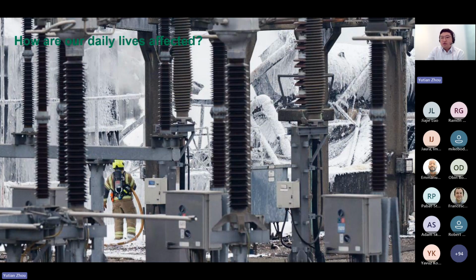While National Grid Electricity Transmission's current standards for fire controls at substation sites prioritize distance and physical barriers between oil-filled equipment, neither of these measures were in place at North Hyde substation, because this is a relatively old substation built prior to those standards being established. Risks at the North Hyde substation were managed by National Grid Electricity Transmission using multiple separate processes, meaning there was no single structured process to provide a cumulative assessment of the overall risk for the whole site.